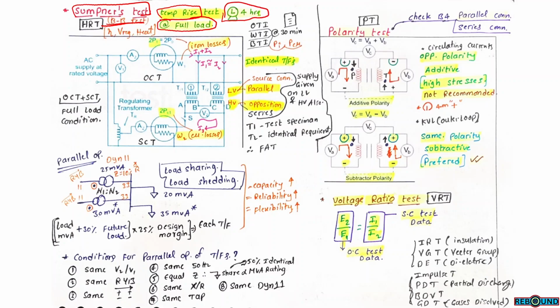So from this test, we can get all the results which are helpful for finding the efficiency of the machine, voltage regulation and heat. This is also known as heat run test, HRT. This is the total arrangement for heat run test. It requires 3 transformers: one regulating transformer and 2 identical transformers. Connections must be as per the circuit diagram.